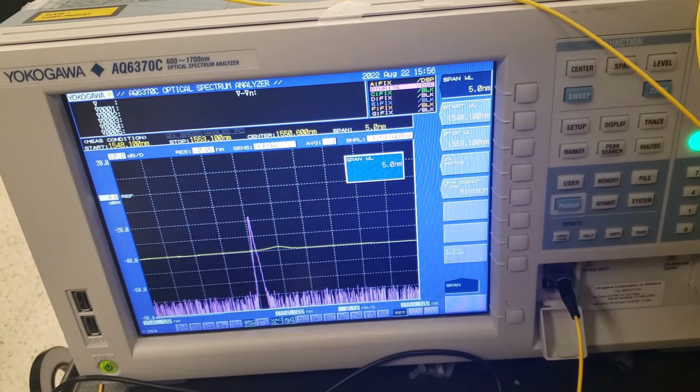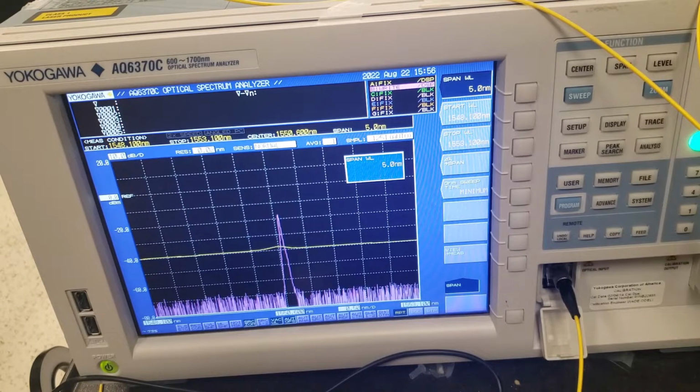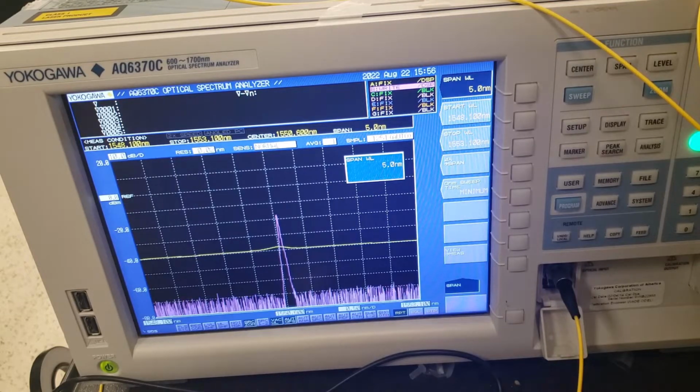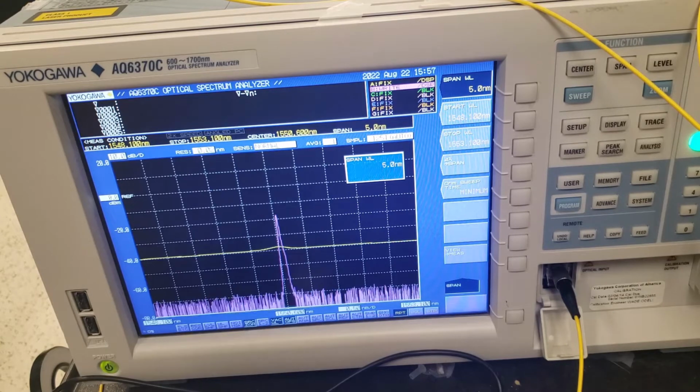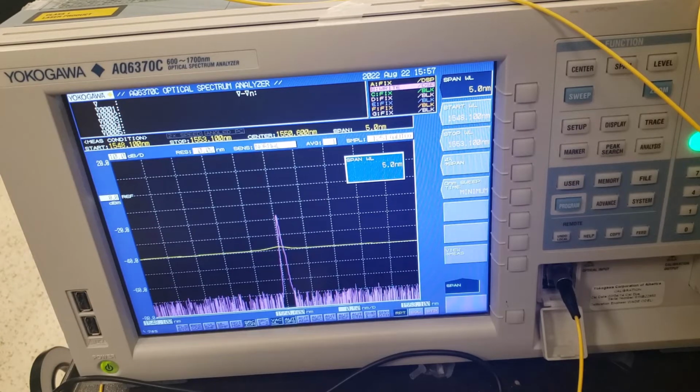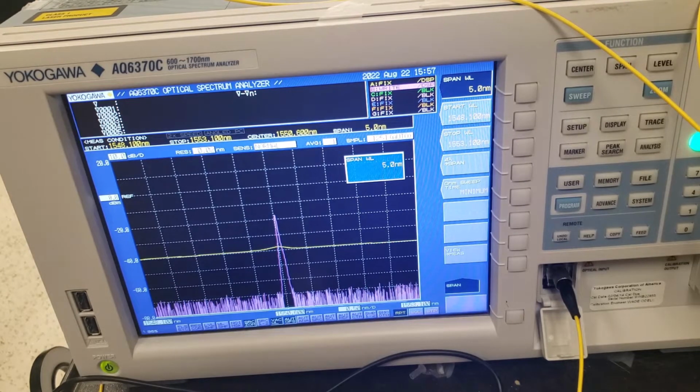So let us increase this a bit. That was maybe a little bit too much. It's still adjusting. Luckily, the software controlling the laser inside of the device that we used in the EOM video lets you simply tune the wavelength using the software, which is quite convenient. I think it needs to be a little bit smaller to be central. So I'm just going to adjust it. That's pretty good, but I think we can do a little bit better. Let's see, okay, that is pretty close. Good, so now the laser is aligned to the central wavelength of the grating.